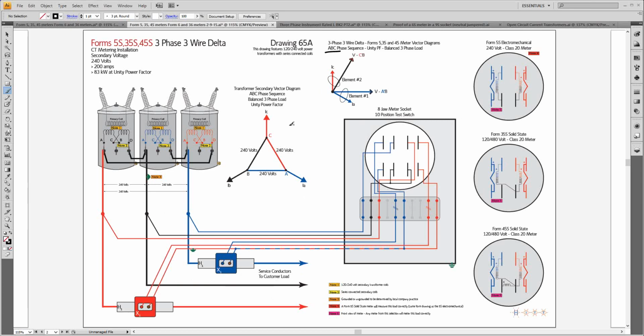And then for the connection to be correct, the conductor that goes unmetered has to have a tie to both of the potential coils in each one of these 2-element meters. And so that's how that goes together as far as the metering, and how a 5S, a 35S, or a 45S would see that load, see whatever load that's connected to it.